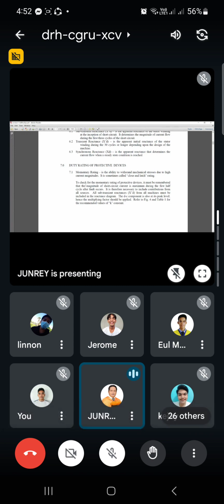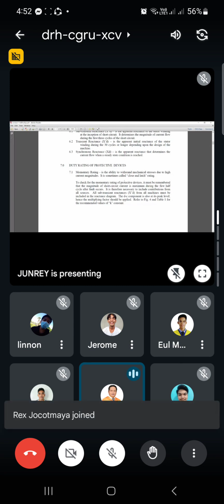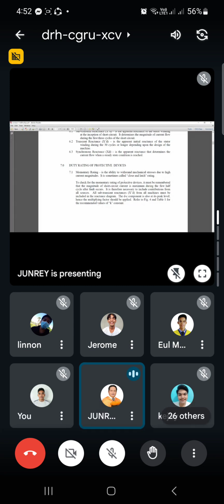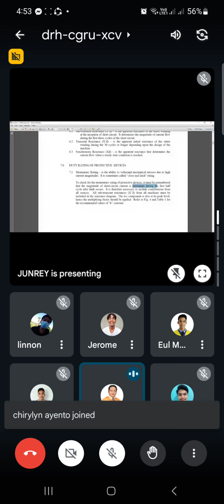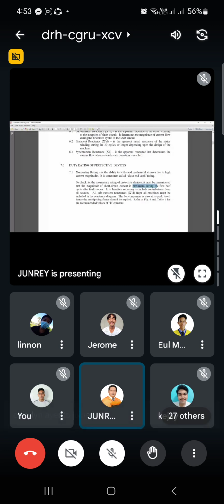Okay, so to check for the momentary rating of the protective devices, it must be remembered that the magnitude of the short circuit current is maximum. So ang imong short circuit current is maximum during the first half cycle after fault occurs. Dili man siya from time to time, permi siyang dako, first few cycles lang. So, first half cycle, maximum ang imuhang short circuit current.